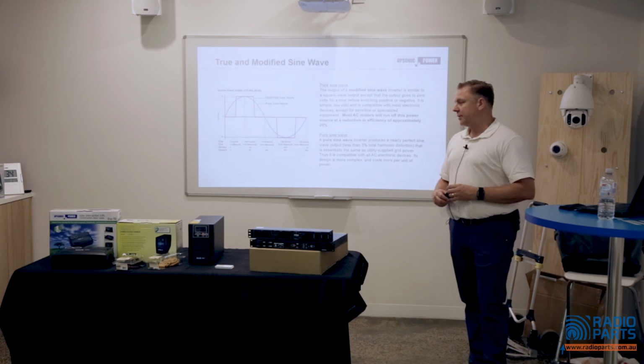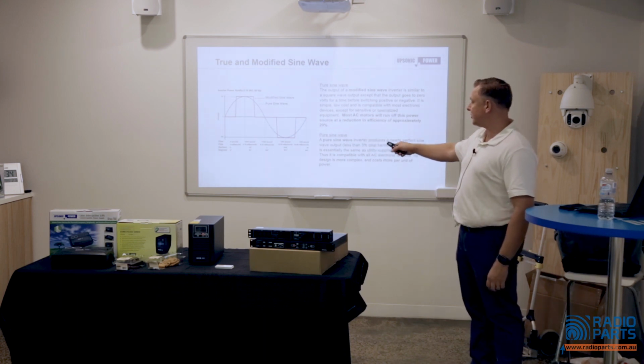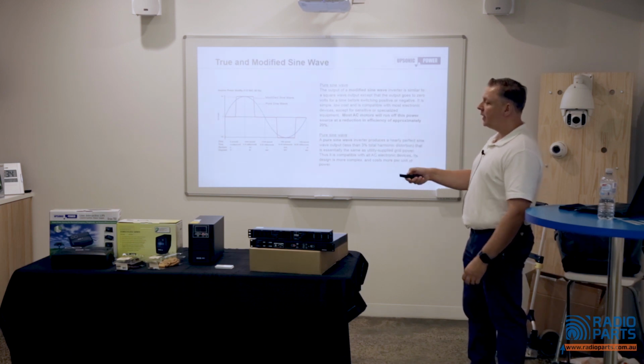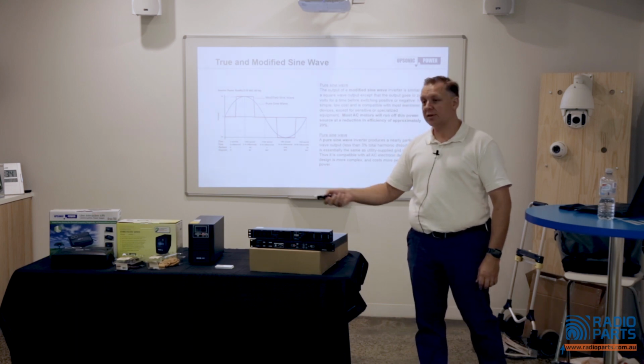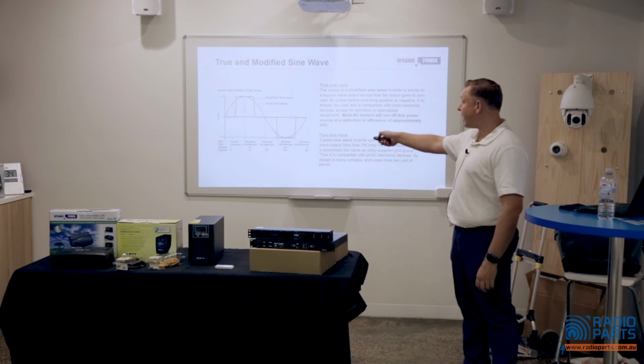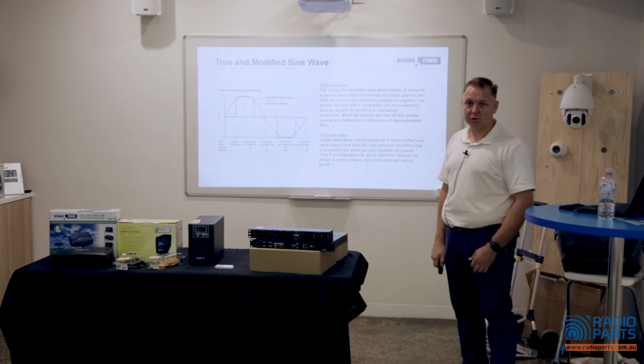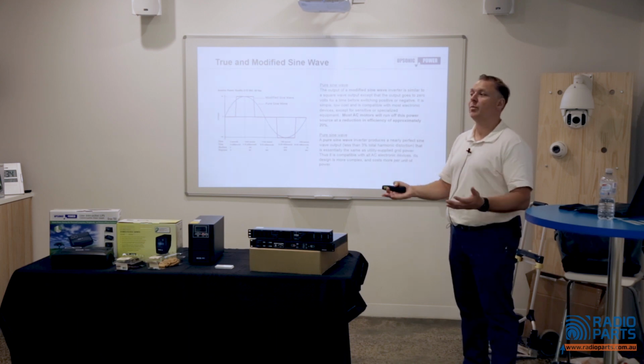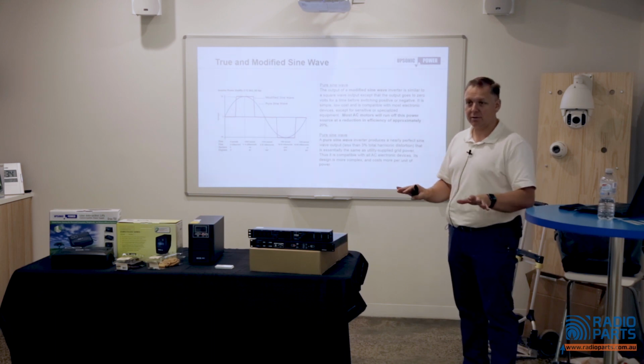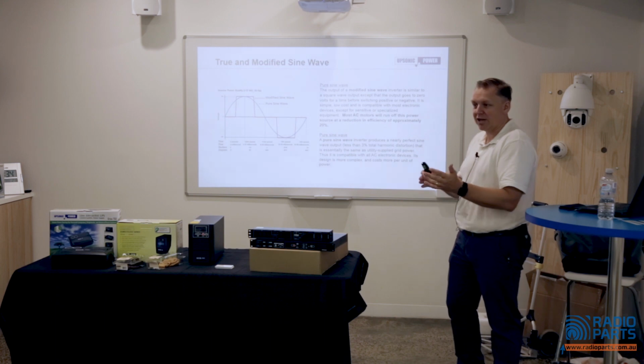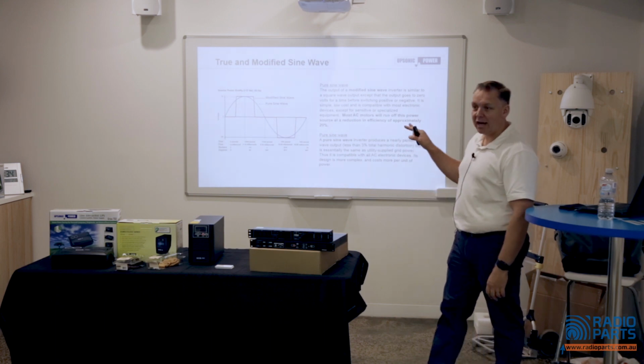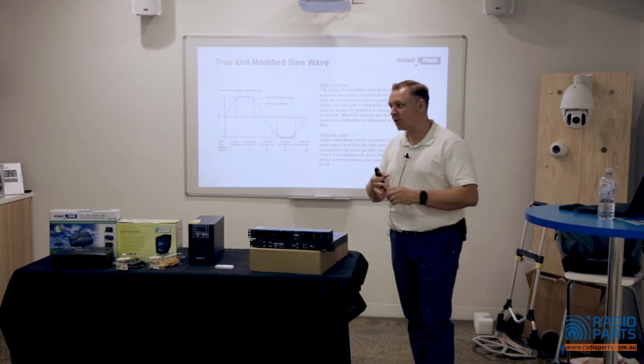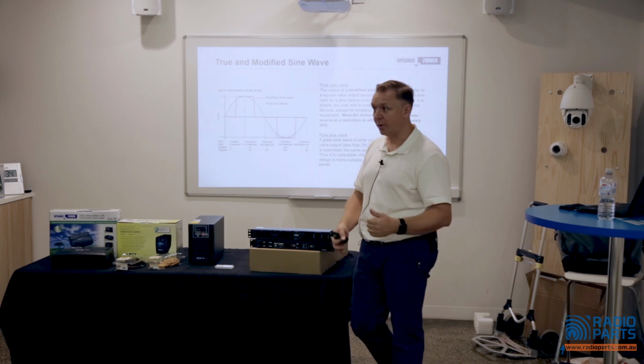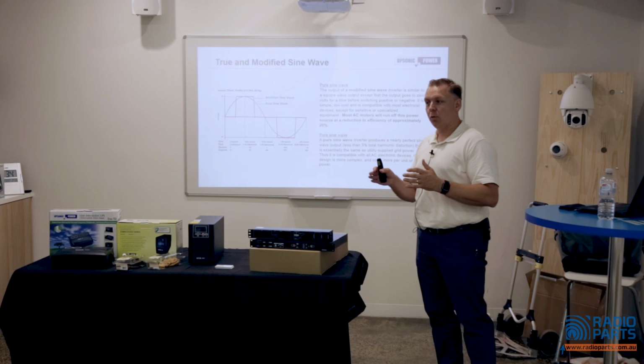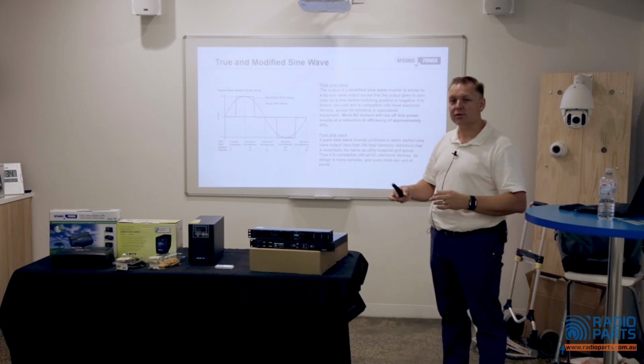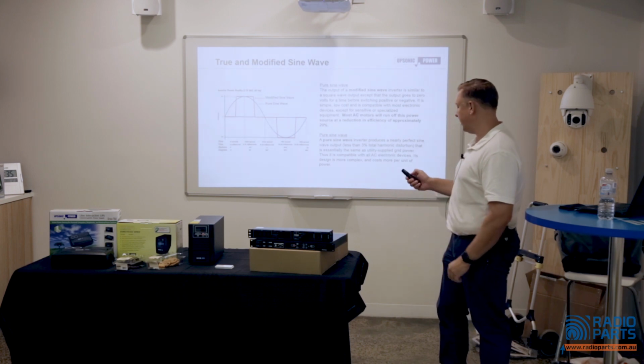True versus modified sine wave. This is another important consideration. We have in blue our nice smooth AC waveform, which is our normal supply. These offline units or standby UPS systems, when they drop onto their batteries, their output looks like the red line. That's called a modified sine wave. Most switch mode power supplies, powered equipment, most computers, they don't care. It just gets the voltage, that's enough for it, since it's changing it to DC internally anyway. Some systems are sensitive to that. You get some switches, some really high performance stuff, some audio equipment. Actually, a lot with audio equipment. That sort of thing will not like that supply, and it causes lots of other issues. It's one of the reasons why when you go to a bigger unit, that's not the case.